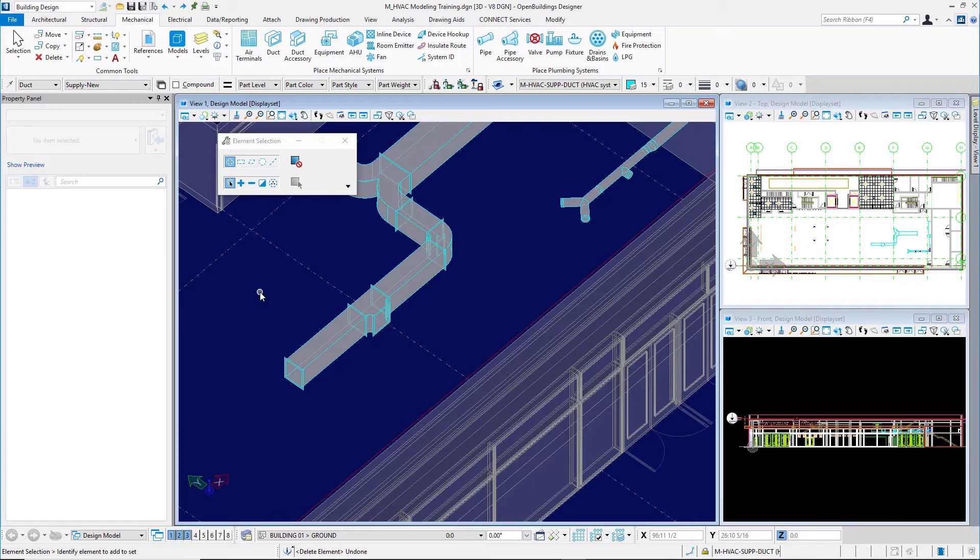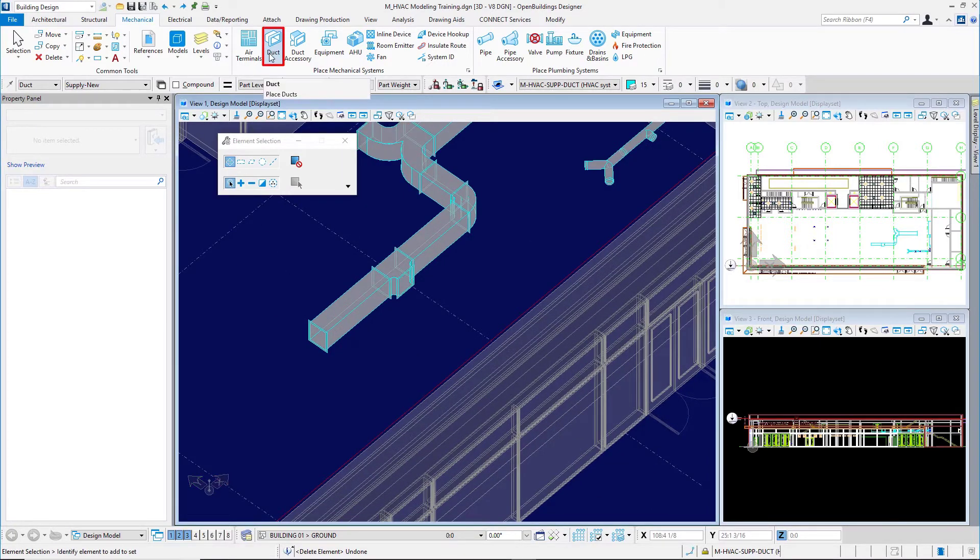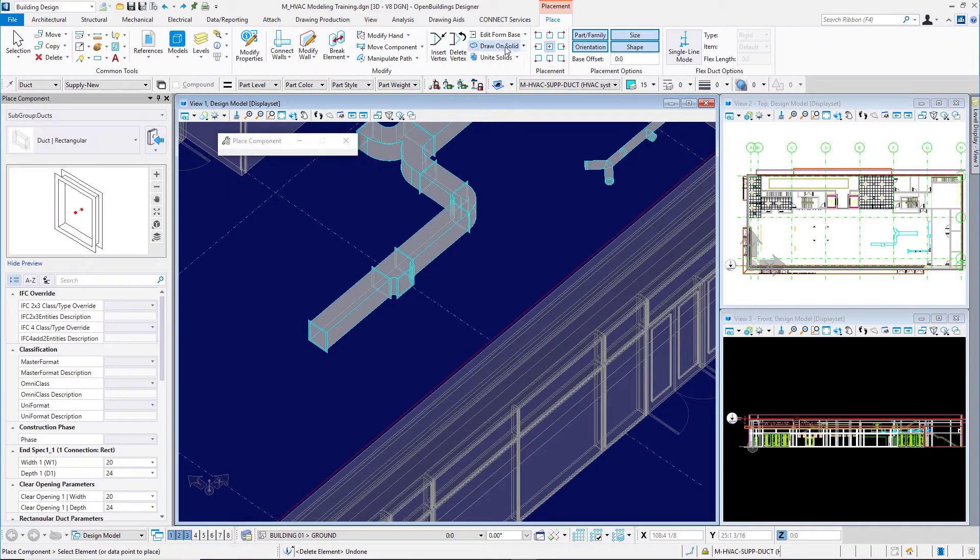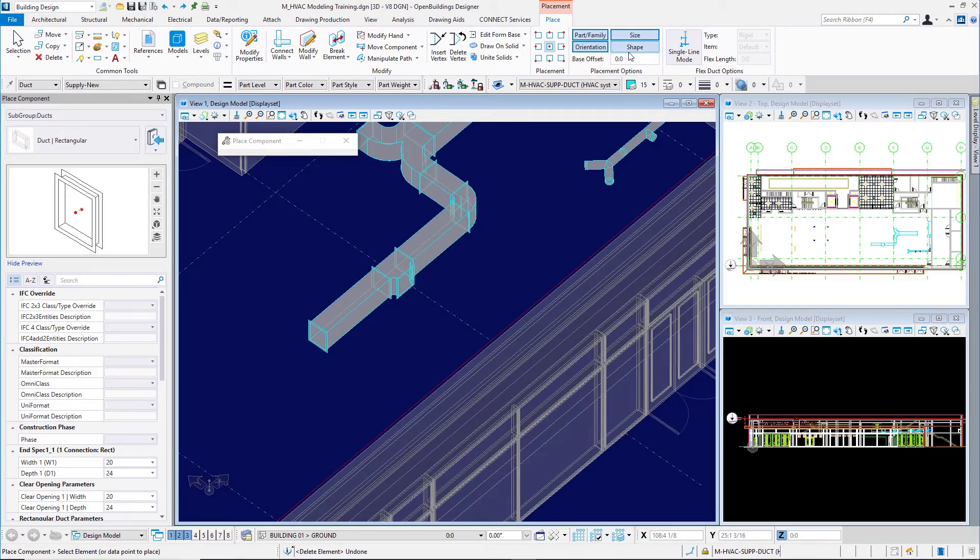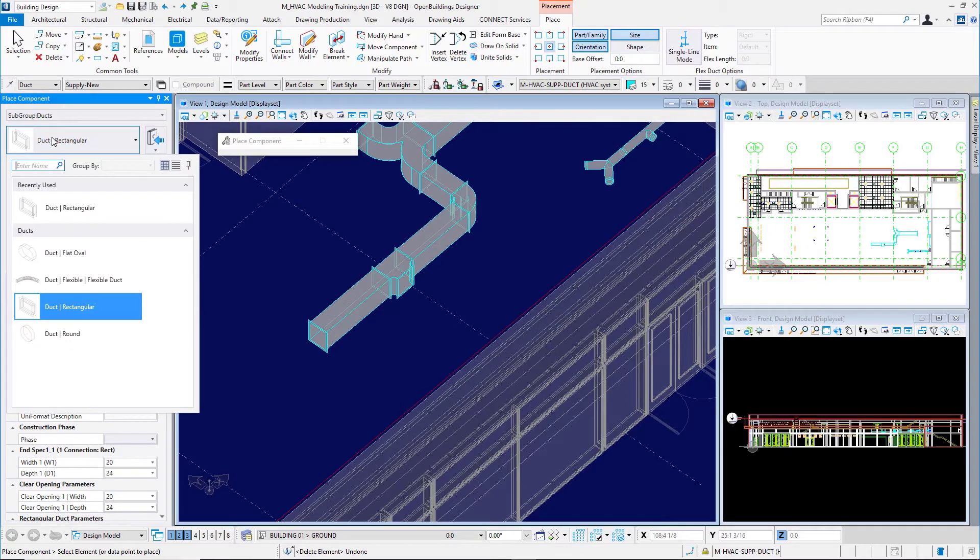I'll place some round ductwork on the duct I've already got out here. I'll come up to the duct command in the mechanical tab of the ribbon interface. This time I'll turn off the shape option here, so I'm not going to match the rectangular shape. I'll choose round ductwork.